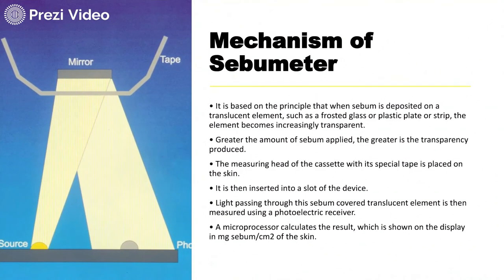The Sebumeter is based on the principle that when sebum is deposited on a translucent element — such as frosted glass, a plastic plate, or a strip — the element becomes increasingly transparent. The greater the amount of sebum applied, the greater the transparency produced. The measuring head of the cassette with its special tape is placed on the skin, then inserted into a slot of the device. Light passes through the sebum-covered translucent element, which is measured using a photoelectric receiver. A microprocessor then calculates the amount of sebum, and the result is displayed in units of milligrams of sebum per centimeter square.